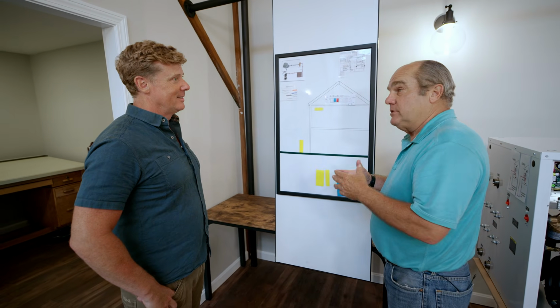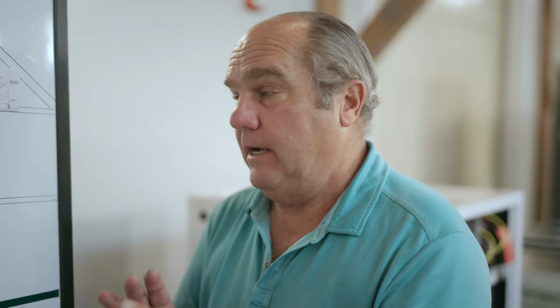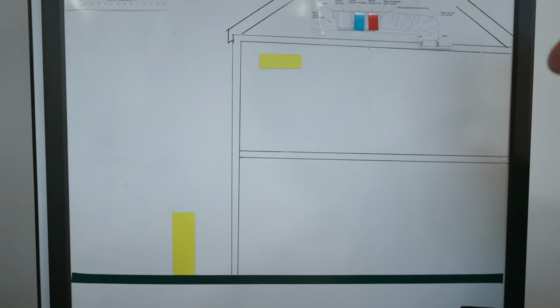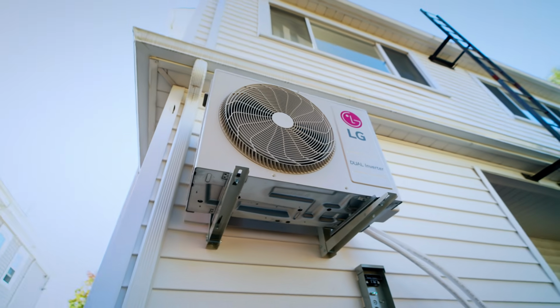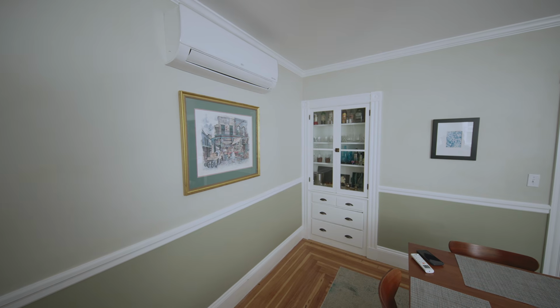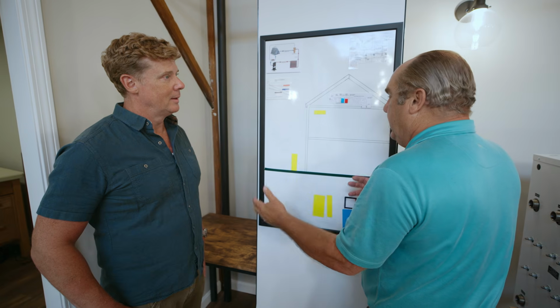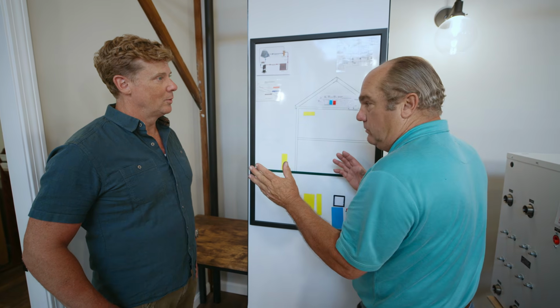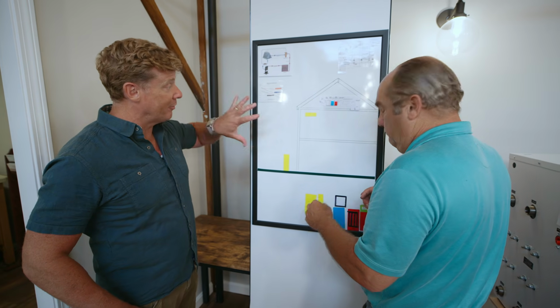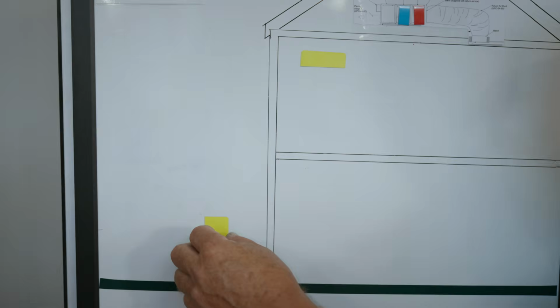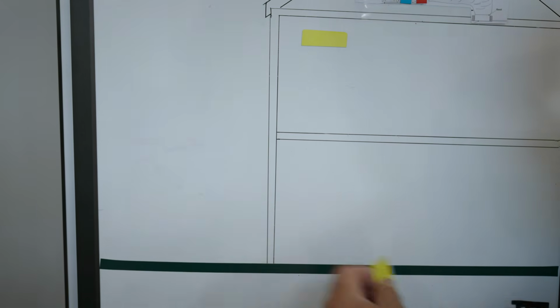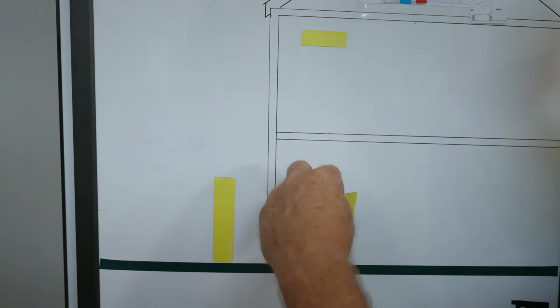A geothermal is just a heat pump. The important thing about a heat pump is they all basically work the same. The only question is what is the source of the heat and what's the delivery method? So it's always going to be air to air, air to water, water to water, or water to air. The most common heat pump we know is air to air. You've seen the condensers outside, you'll see the high sidewall units. Often it's just got refrigerant piping between the two, and it either heats or cools. And when you say air to air, that's because it's getting or dumping the heat from the air outside to condition the air inside.